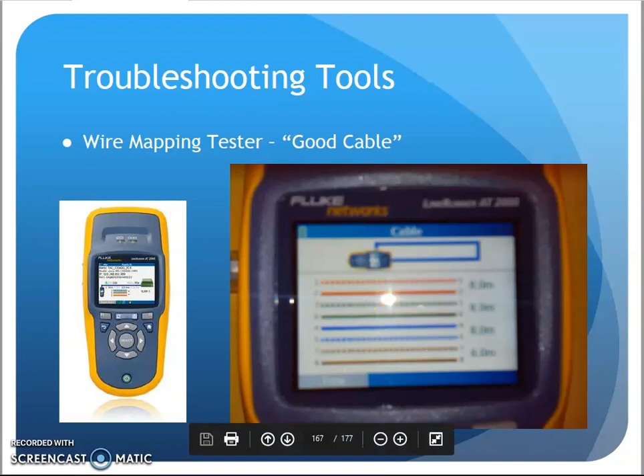Here is a short between two wire pairs, showing a short between the 1 and 2 cable. And here the two wires are flip-flopped, reversed, the white and brown got reversed in the termination somehow, which is really easy to do. That shows as a reverse pair.